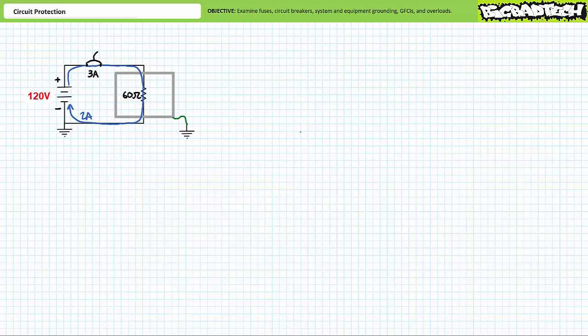Let's say the device draws 2 amps as previously and an operator reaches inside the electrically neutral frame and touches the energized electrical innards. Let's say this unfortunate person completing a path draws 30 milliamps of current, an extremely dangerous, painful, and damaging amount. As previously, despite this dangerous occurrence, the rated current of the circuit breaker servicing this machine is not exceeded and the circuit breaker will not trip. Again, a traditional circuit breaker only protects the system from overcurrent events associated with short circuits.